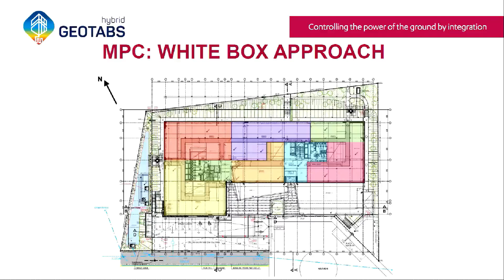What MPC is really strong in is avoiding the destruction of energy. For example, if one side of your building needs heating and the other side needs cooling, and hydraulically it's possible to bring energy from one side to the other, that's something MPC is always going to do. It will also check, if you have floor heating and ventilation, that one isn't heating while the other is cooling, except if that's truly optimal, which might be the case but is not often so.